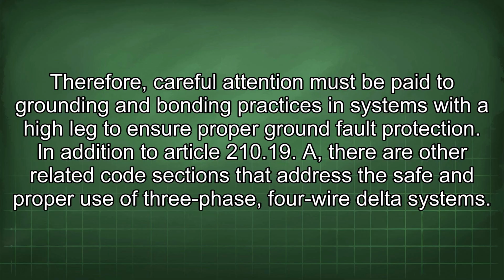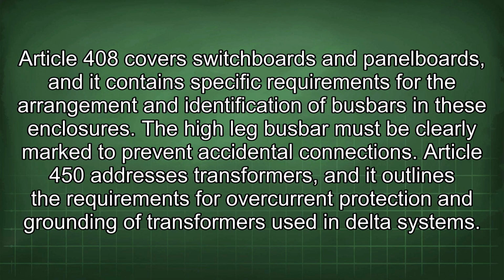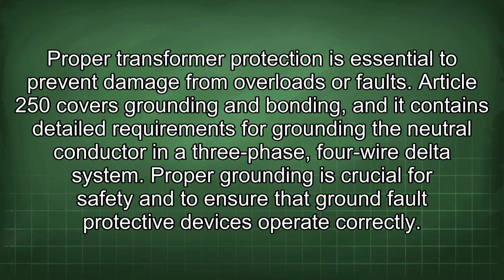In addition to Article 210.19(A), there are other related code sections that address the safe and proper use of three-phase, four-wire delta systems. Article 408 covers switchboards and panelboards, and it contains specific requirements for the arrangement and identification of busbars in these enclosures. The high leg busbar must be clearly marked to prevent accidental connections. Article 450 addresses transformers, and it outlines the requirements for overcurrent protection and grounding of transformers used in delta systems. Proper transformer protection is essential to prevent damage from overloads or faults.